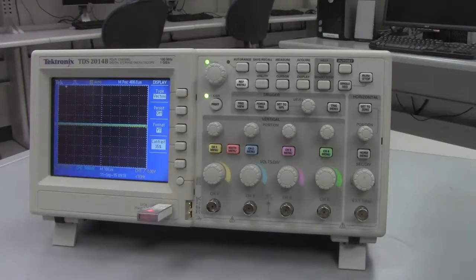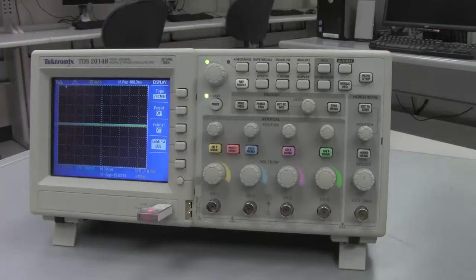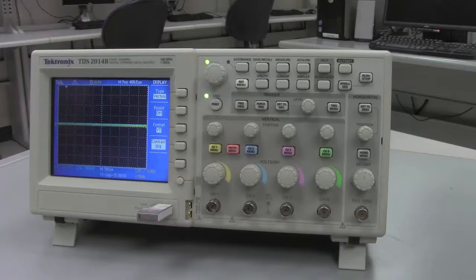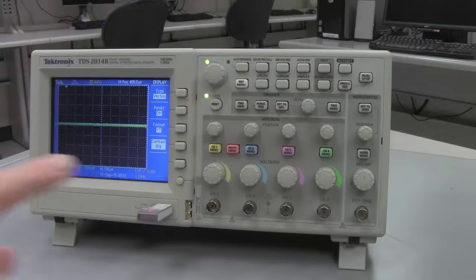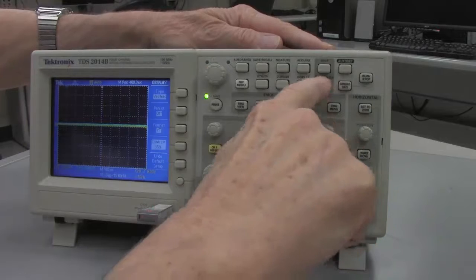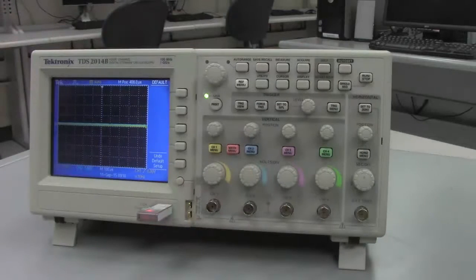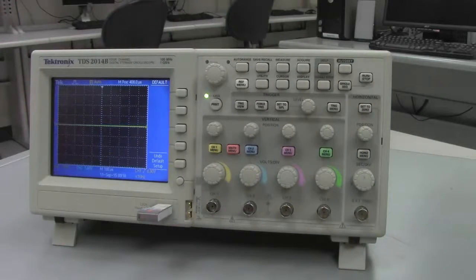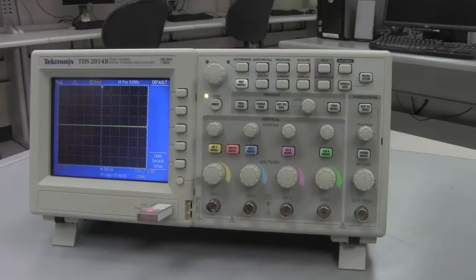Having done that, again, we don't know exactly the condition that it came up in. What were the settings before? There's a default setup button on this, and when you walk up to a new scope, go ahead and just push the default setup button and bring it to a known condition. It takes just a second, and it's then ready to go.